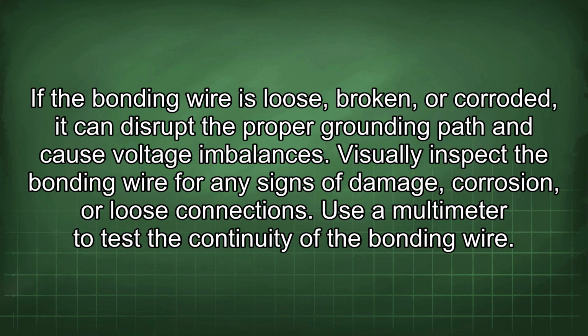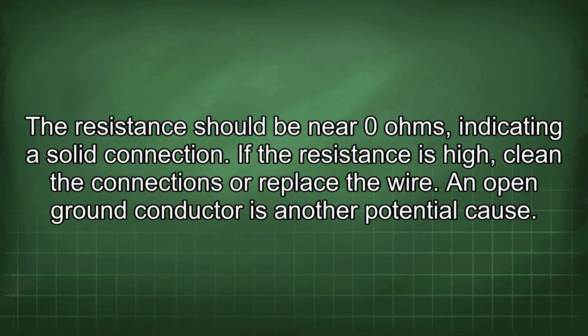Visually inspect the bonding wire for any signs of damage, corrosion, or loose connections. Use a multimeter to test the continuity of the bonding wire. The resistance should be near 0 ohms, indicating a solid connection. If the resistance is high, clean the connections or replace the wire.